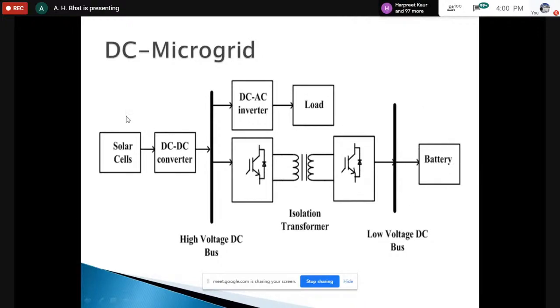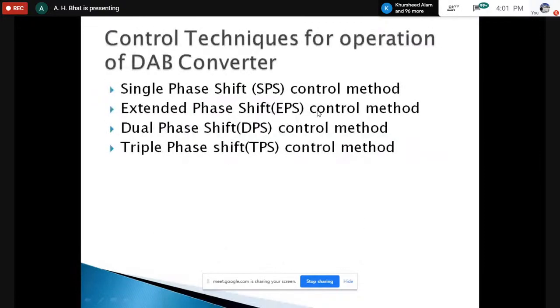And whenever there is a deficiency of power here, the load demand is taken care of partly by this, but it is not able to take care of all the load demand. The rest has to be supplied by the battery storage system. Whatever energy is stored in the battery has to be supplied to the load, meaning power has to flow from low voltage bus to high voltage bus, and then when power comes at the high voltage bus, it is fed to the load. This is how a DAB does it.